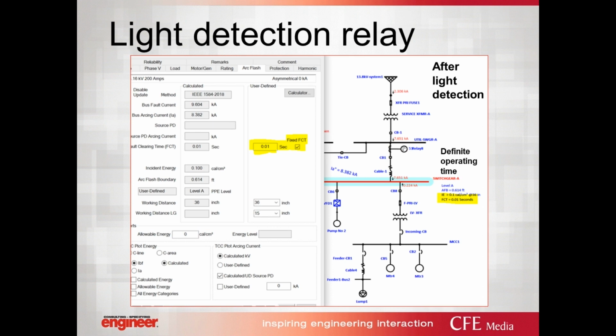As you see, the result for sure, since we are bringing the FCT lower from 0.75 to 0.01, is that we are reducing the incident energy from 7.5 to 0.1. Therefore, again, a typical application may be in medium voltage, and it is an effective way to reduce the arcing current, arcing FCT, and consequently the incident energy. That was the several mitigation approaches, based on the time that we had. I'm sure there are a few more, and that's what we had for today.